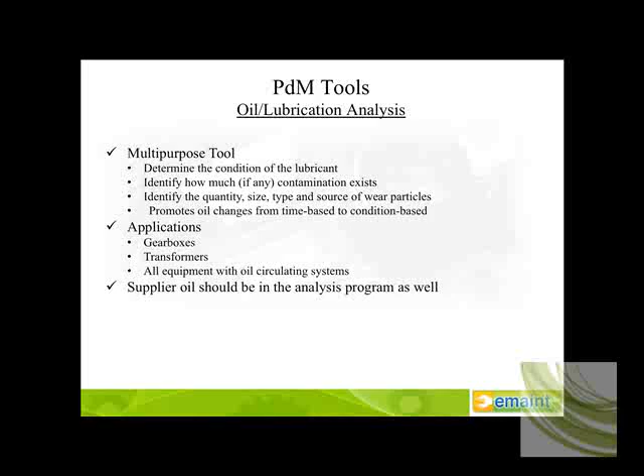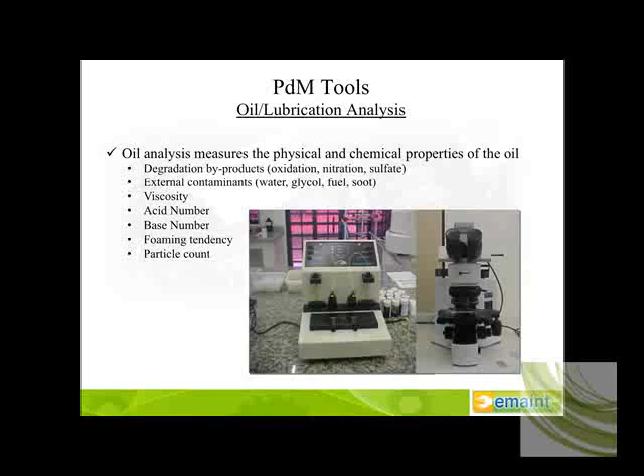Measures the physical and the chemical properties of that oil. Degradation of the byproducts in there, what type of oxidation, nitration, sulfates are in there. These laboratory instruments have the capability of determining what the viscosity is, acid number, base number, foaming tendencies, what the volume of water is within oil, and then, as we've mentioned a couple of times, particulate count also.